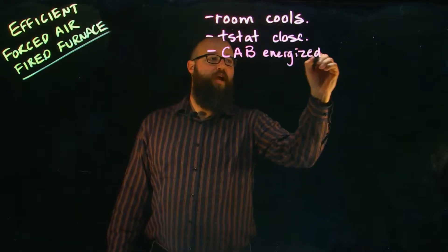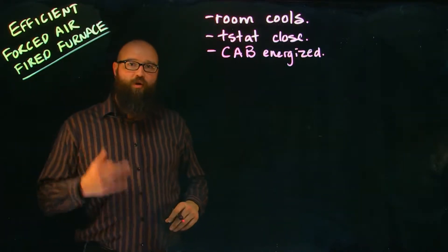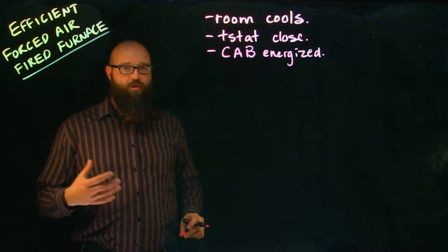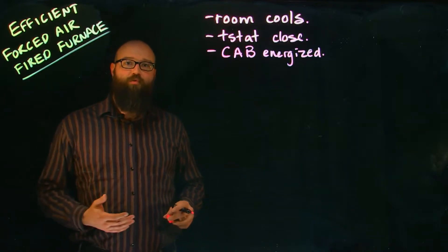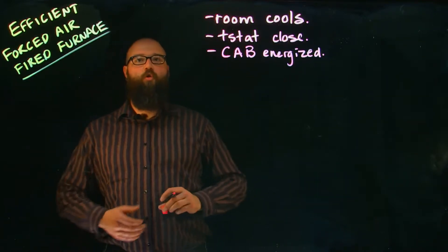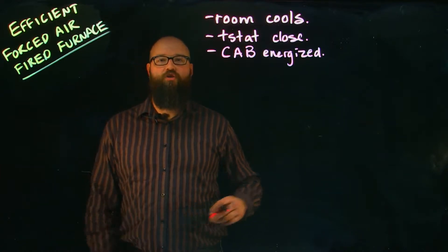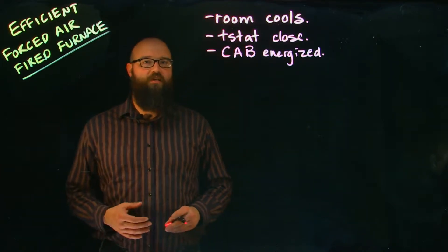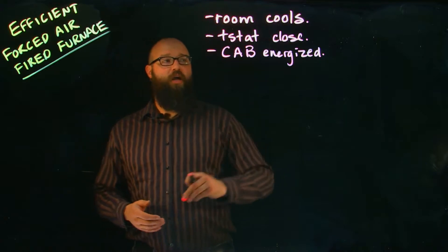The purpose of our combustion air blower is to move those products of combustion across our burners, but it also does a pre-purge where it removes any products of combustion or old gas that might be present in the heat exchanger or the flue itself. Prevents things like explosions. So our CAB is energized.